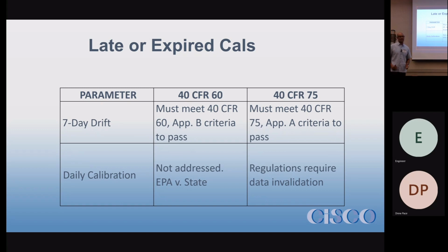So for example, what to do if you ran a calibration and the 24 hours expires, what does Part 60 say to do on the matter? It doesn't make any statement on it. Part 75 makes it clear if a calibration expires, the data starts to be invalidated. As we go along, I'm going to address this a little further on, but generically, the reason why I have that EPA versus state is because now we have information from the state, based on that slide I showed you guys yesterday regarding the various states and agencies we've contacted. Now we at least have a general guidance from different states on how they want to handle it. But in general, you want to be doing calibrations every 24 hours under 60 so you don't have to address that issue.